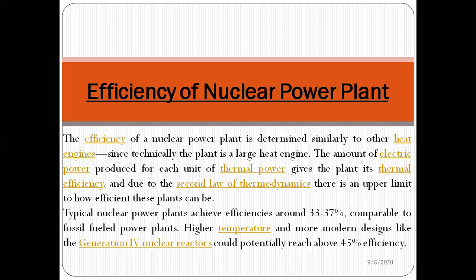The last point is the efficiency of the nuclear power plant. Efficiency is determined similarly to other heat engines - technically the plant is a large heat engine. The amount of electrical power produced for each unit of thermal power gives the plant its thermal efficiency. According to the second law of thermodynamics, there is an upper limit. Currently, nuclear power plants have an efficiency of around 33 to 37 percent, comparable to fossil fuel plants. More modern designs could potentially reach 45 percent efficiency.